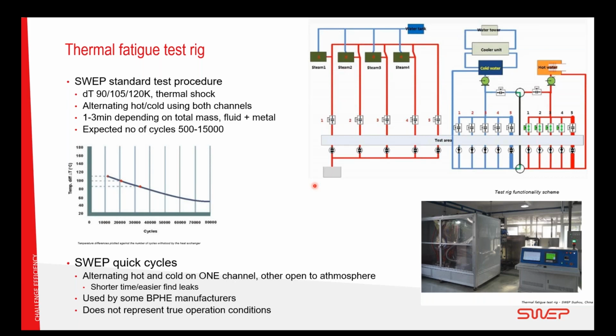There's also a secondary test, we call it the quick cycle, where we alternate the hot and the cold fluid in one channel only, and the other channel is open to atmospheric. It's a shorter time because less time is needed to heat and cool the heat exchanger. It's also easier to find the leaks because it leaks into the other channel, which is open.